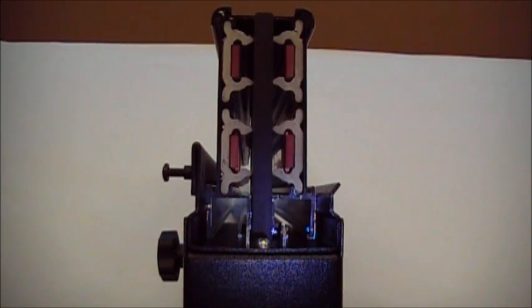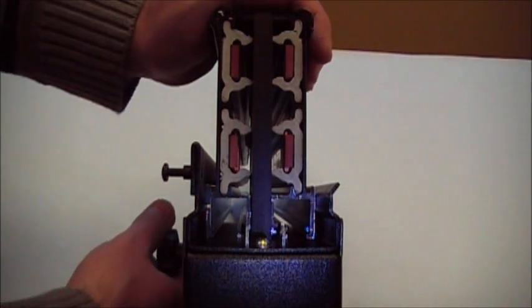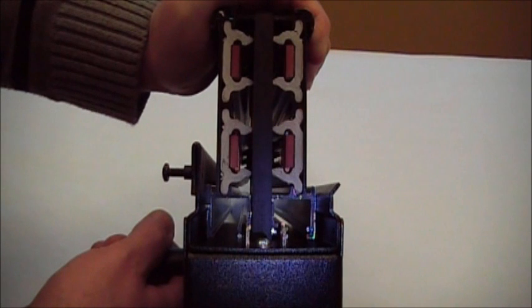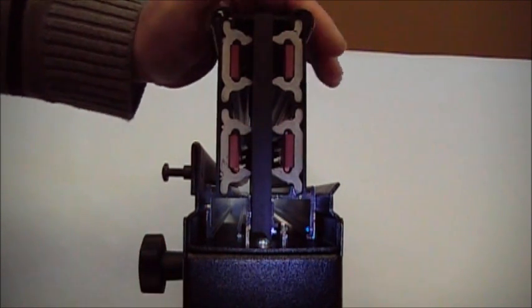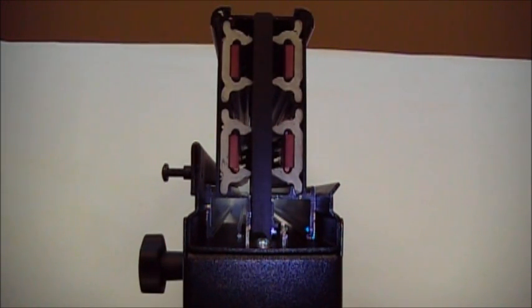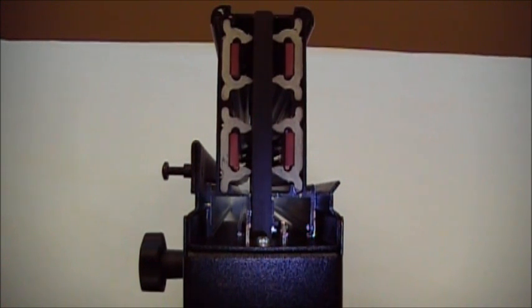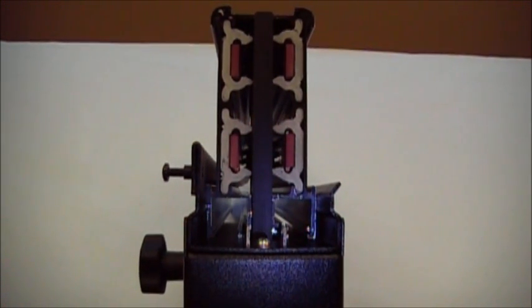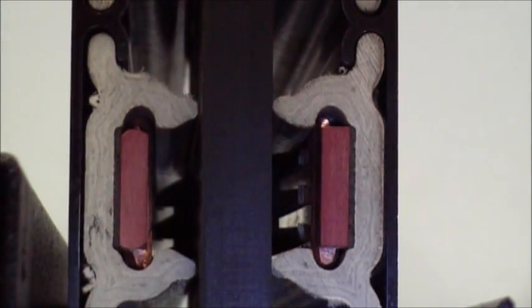One of the key aspects of a busway system is how the plug-in attaches or fixes itself to the busway itself. So we're looking at the PowerWave bus system from the side with the plug inserted, and we will actuate the mechanism that turns the fingers on the paddle that makes contact with the flat bus bars on the side of the busway. And as we zoom in, you'll be able to see how the fingers are making connection to the bus bars.